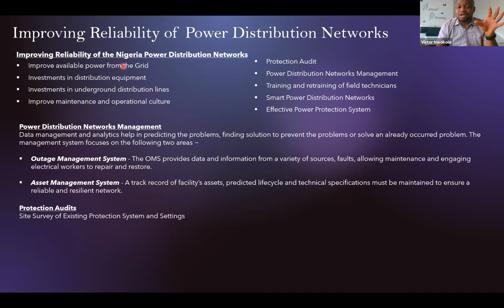There's no proper protection system. We just have wire fuses on most of those feeder pillars, so they're not giving sufficient protection. Even the protection on the 11 kV supply line, some of them are not properly rated. So transformers get overloaded and they blow eventually. So in that case, the reliability of the system is what failed rather than the available power. Thank you very much.